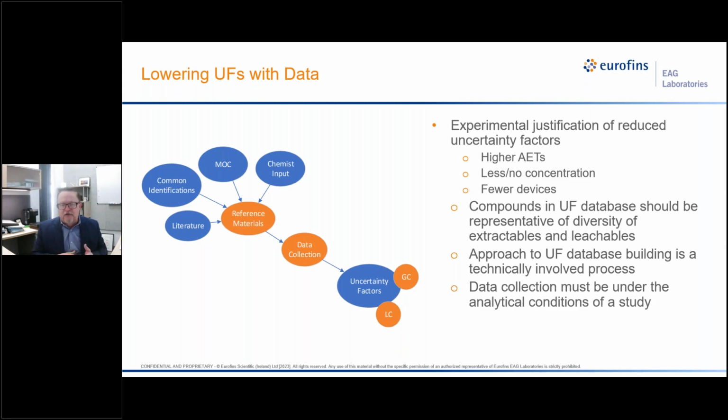We've read literature that suggests LCMS can have an uncertainty factor of 10, and it's kind of commonly accepted and really isn't challenged if you use 10 in your calculation. Most people believe it to be conservative enough. Ultimately, though, if you collect data under controlled experimental conditions using a validated method that you validated, and you collect that data in the same fashion, you should be able to demonstrate that your instrumentation uncertainty factor is much lower.